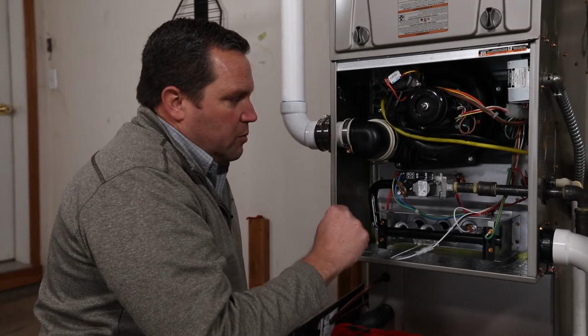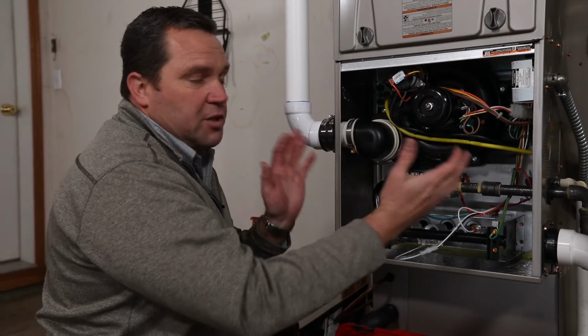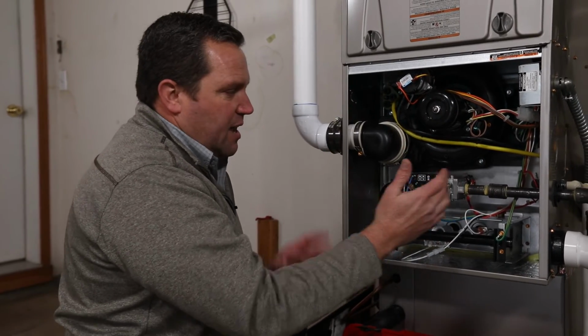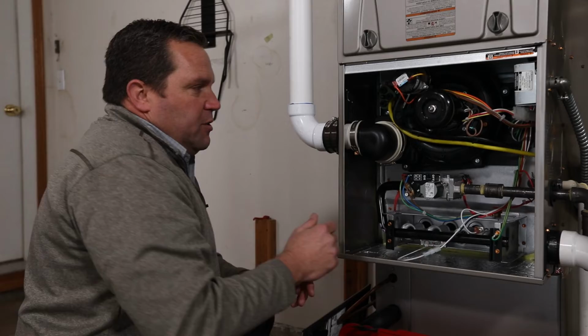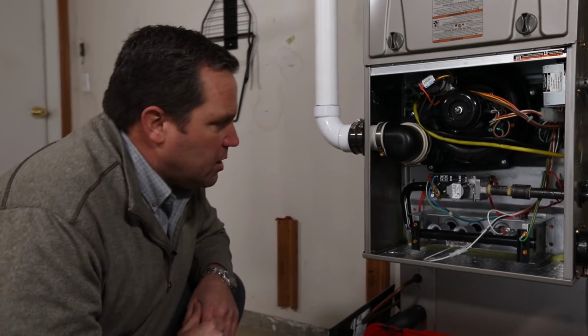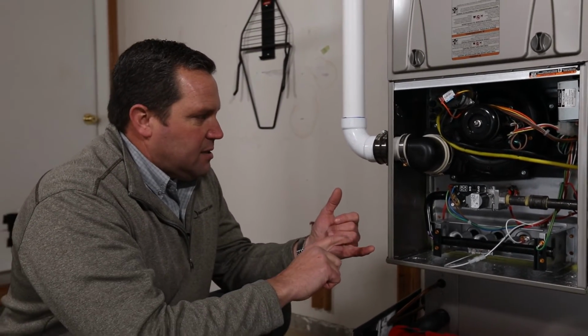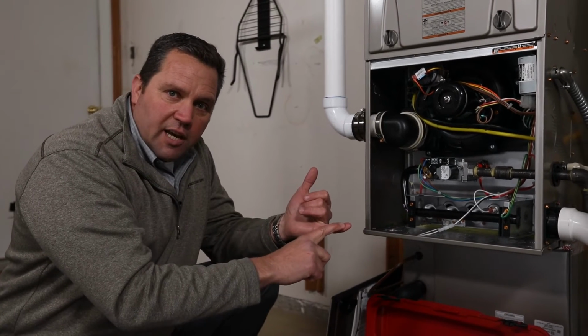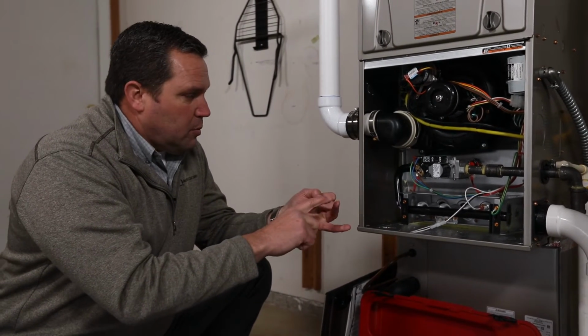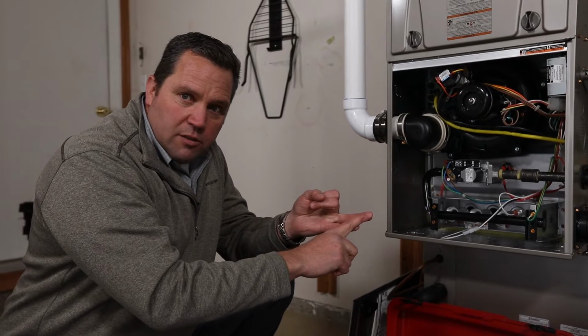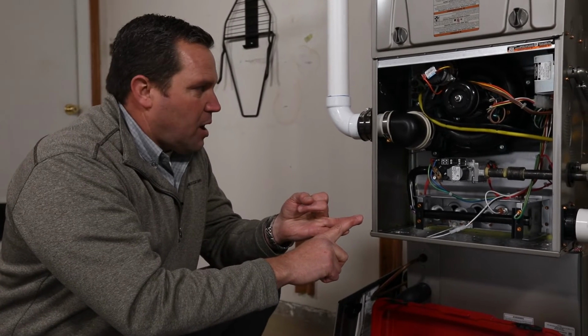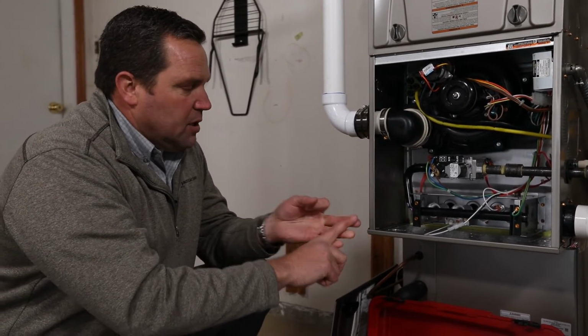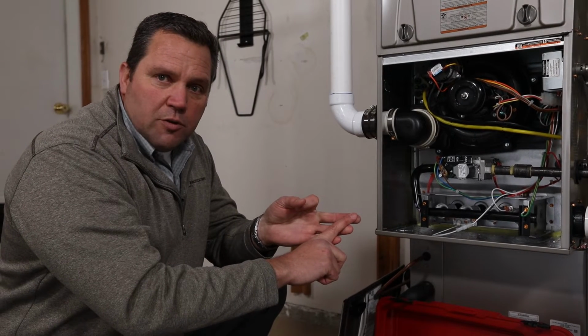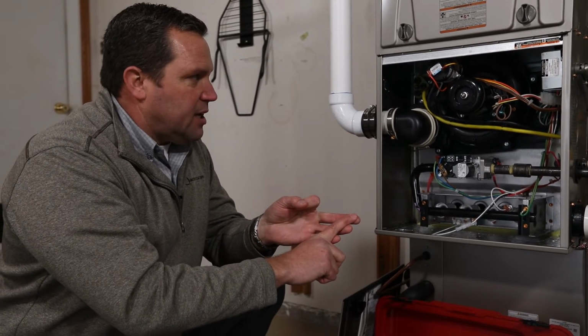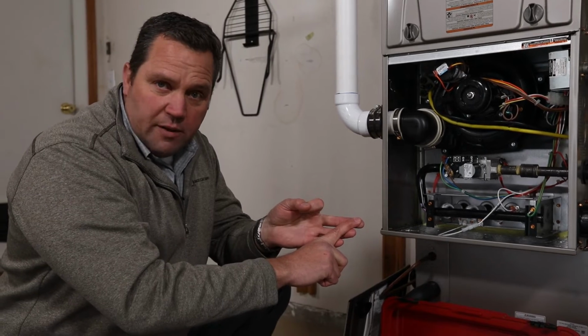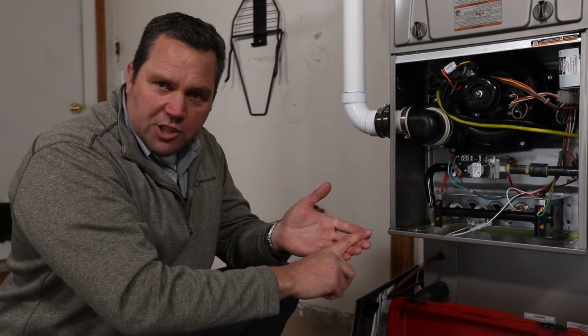So what we look for when we come out to a system, and this is a new system, so we're not going to have any issues here. But if you've got a system that's a little bit older, we look at the igniter to make sure the igniter is in good shape. We look at the high limit switch to make sure that it is connected properly and operating properly. We look at the inducer draft motor to ensure that it's got good operation, that it's turning at the RPMs that it should be. And then we check the heat exchangers.